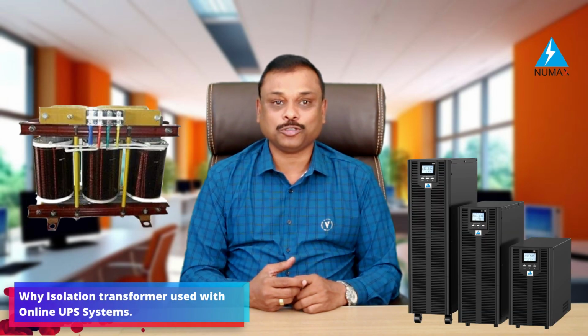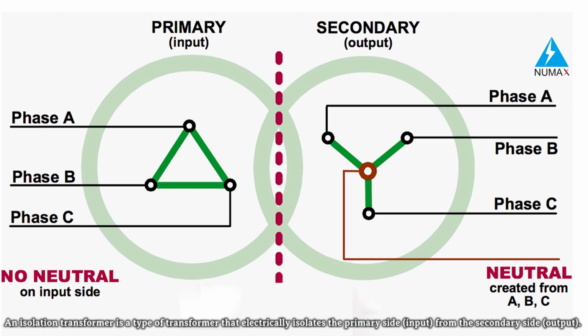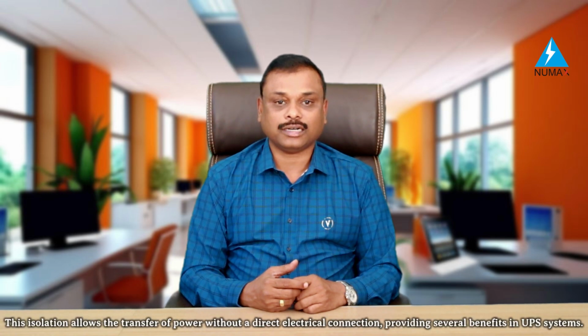In this episode, I'll briefly explain why an isolation transformer is used with an online UPS system. An isolation transformer is often used with online UPS systems to enhance performance, safety and power quality. What is an isolation transformer? An isolation transformer is a type of transformer that electrically isolates the primary side input from the secondary side output. This isolation allows the transfer of power without a direct electrical connection, providing several benefits in UPS systems.